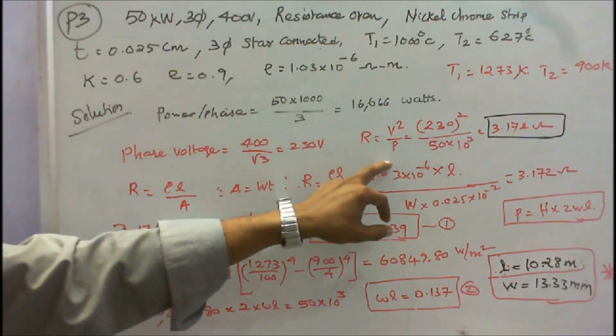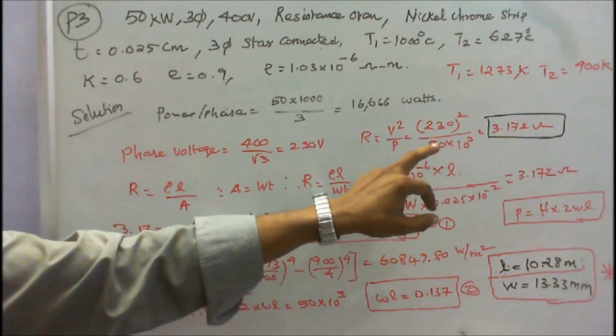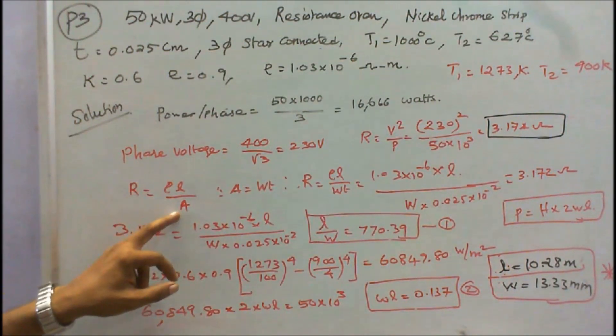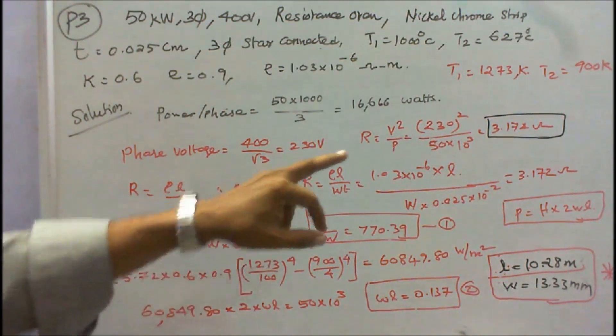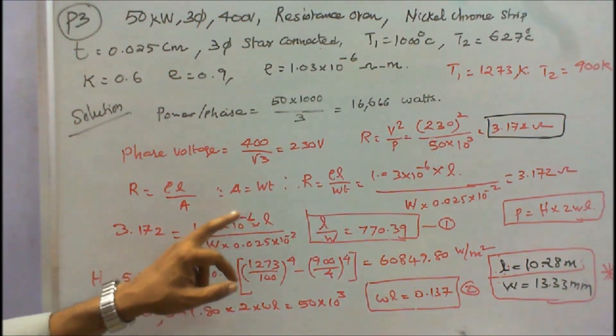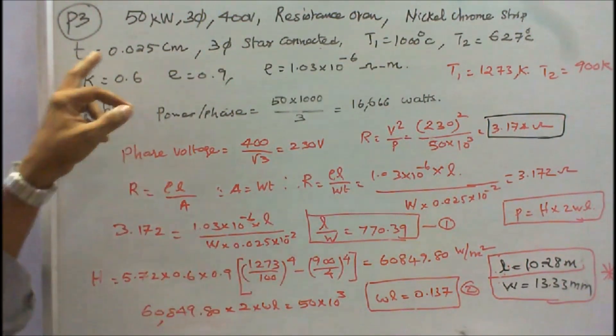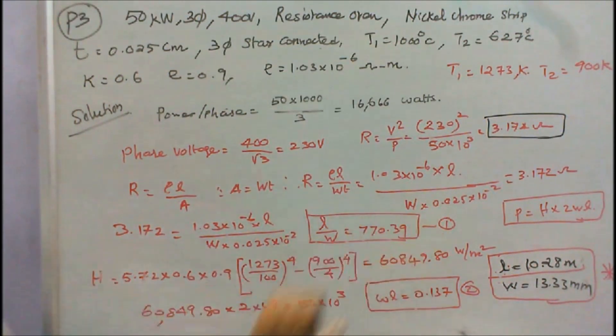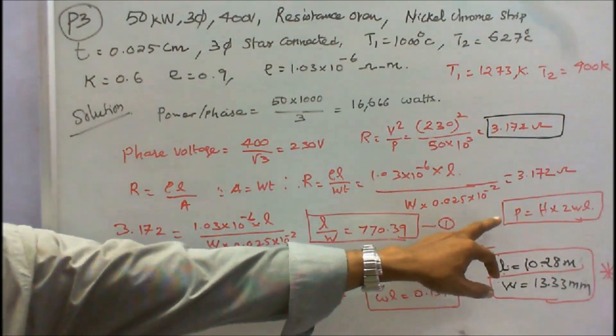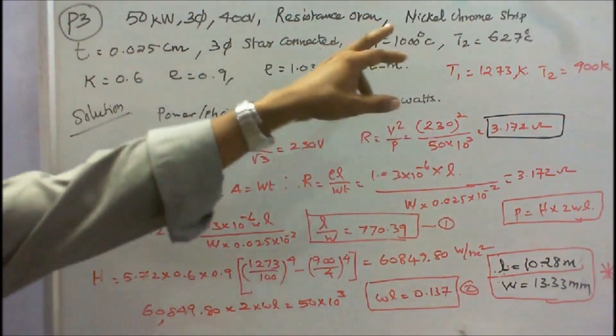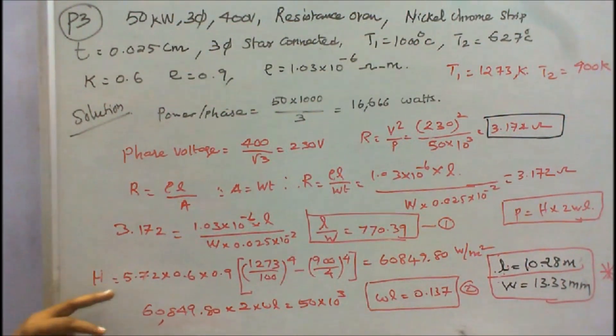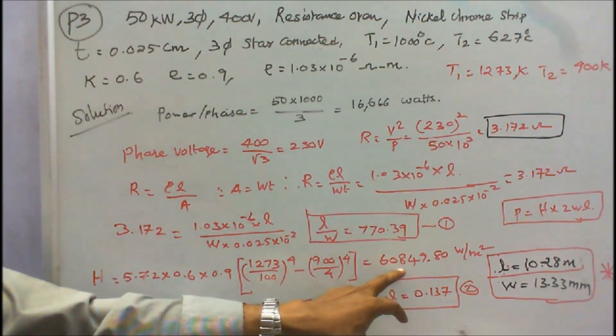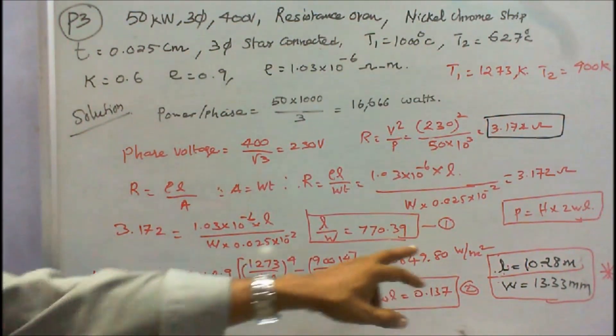R equals V²/P, where phase voltage is 230V and power per phase is used, giving R equals 3.172 ohms. Since R equals ρL/A and A equals W × T, substituting gives: 3.172 equals 1.03×10⁻⁶ × L divided by (W × 0.025×10⁻²), so L/W equals 770.39. This is equation 1. Under thermal equilibrium, H is calculated using the radiation formula with T1 and T2, giving H equals 60,849.80 W/m².